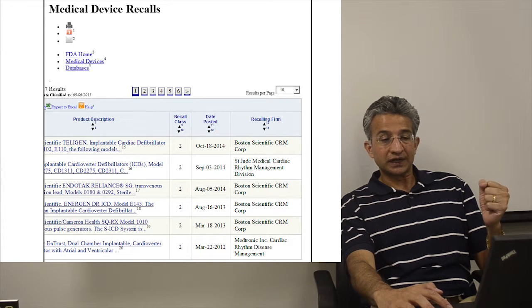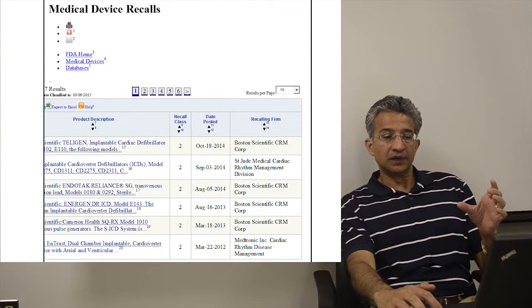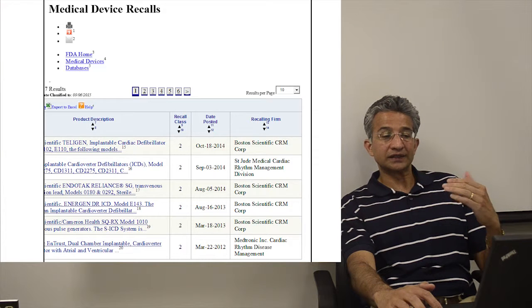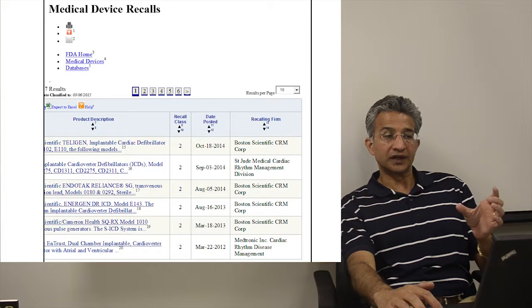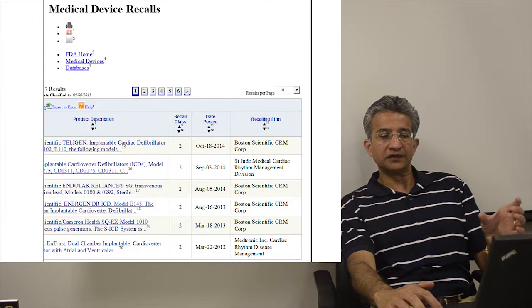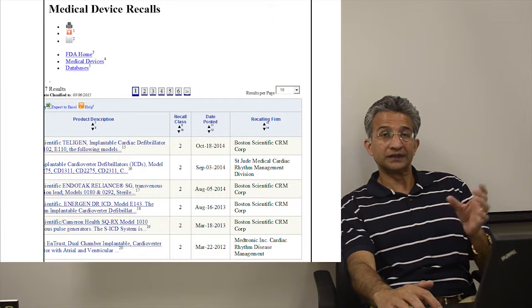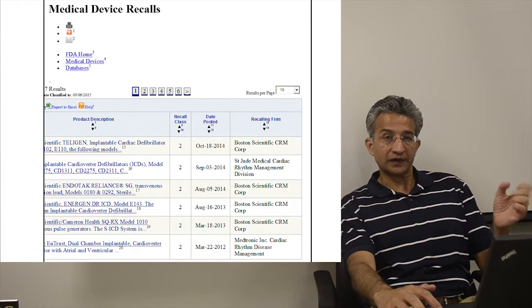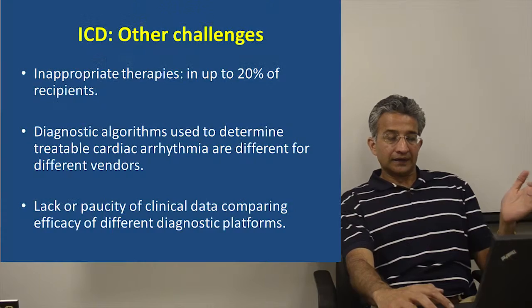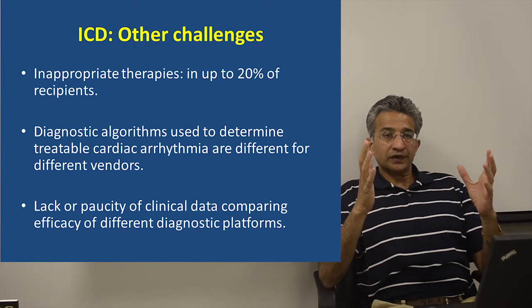And the challenges are several, but this is the one place where this particular heart simulation platform can be a perfect tool, where prior to field trials, we can actually test out the different device components by mimicking the different clinical scenarios several times over to test the platform very rigorously for the different features that are in there. And in doing so, if we can decrease the recalls by even half, that's a significant improvement on what is currently available to us.